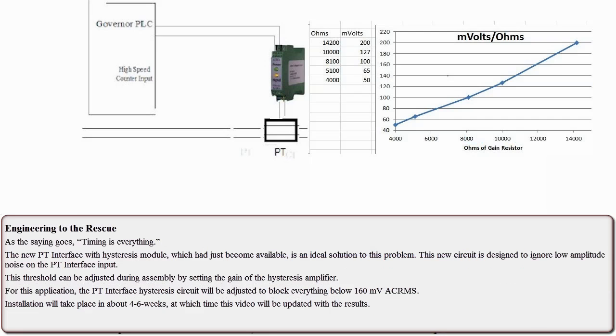As the saying goes, timing is everything. The new PT interface with hysteresis module, which had just become available, is an ideal solution to this problem. The new circuit is designed to ignore low amplitude noise on the PT interface input. This threshold can be adjusted during assembly by setting the gain of the hysteresis amplifier. For this application, the PT interface hysteresis circuit will be adjusted to block everything below 160 millivolts ACRMS. Installation will take place in about 4 to 6 weeks, at which time this video will be updated with the results.